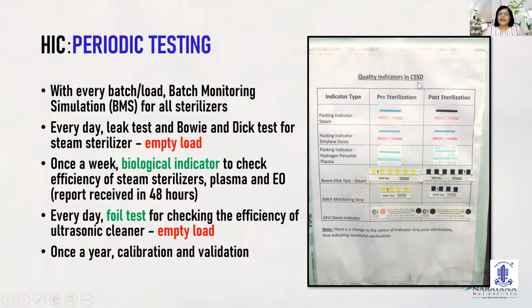At the same time, when it comes to the quality indicators in CSSD, let's see how it goes. So if you have a packing indicator over here, the pre-sterilization blue line gets converted into a black line over here, which basically means that everything is okay. Packing indicator with ethylene oxide, from this blue line, the color change happens. The packing indicator for hydrogen peroxide, if you have a plasma sterilizer, then from this line, the color changes to a lighter color. The Bowie-Dick test from the steam, from yellow, goes to a darker black color. Batch monitoring strip, which is used, goes from yellow to a dark black color. And MVI steam indicator from pink goes to a dark color. This change of the color of the indicator strip post sterilization indicates successful sterilization.